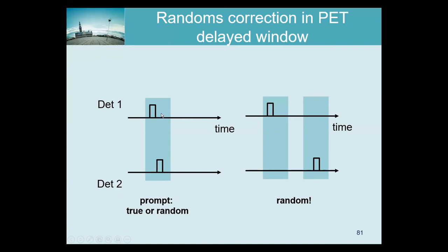Of course, it could be that both detected events are unrelated singles that happened to fall in the same time window — that's a random. To estimate how often this happens, you slightly shift the coincidence window by about a microsecond. You use exactly the same electronics and tell the camera: detect something here, then check for a detection in the shifted window. In a microsecond not much changes in the patient, so any coincidence found must be a random, since no true pair can span a microsecond.